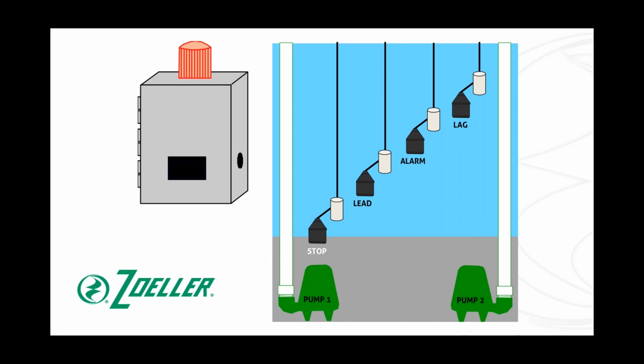What you will notice is we have separated out the alarm and the lag functions onto their own float switches this time. That's the difference between a 3-float and a 4-float system. So what I want you to also note here is that I have opted to set my alarm float before my lag float.